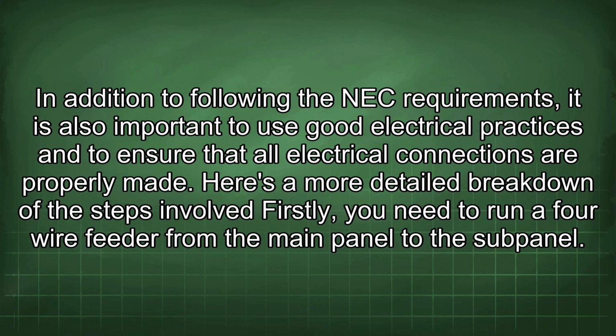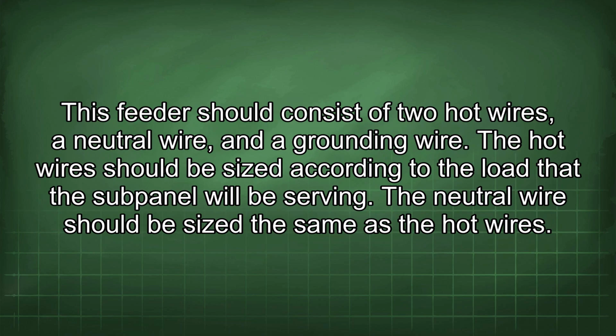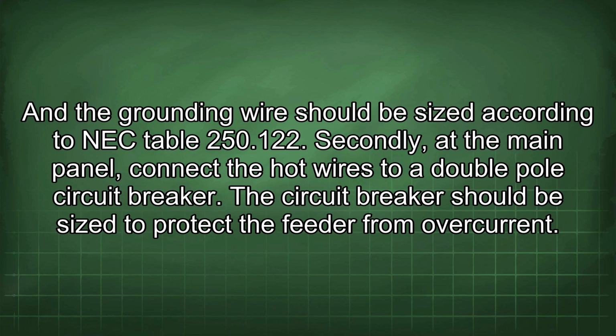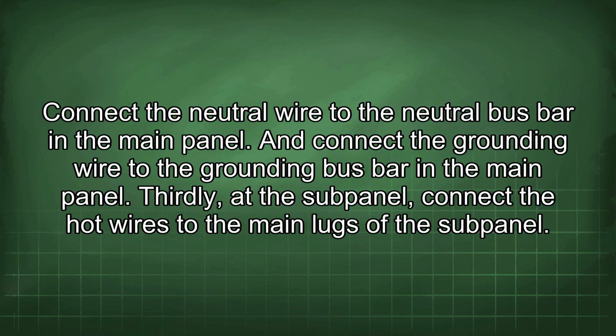Firstly, you need to run a four wire feeder from the main panel to the subpanel. This feeder should consist of 2 hot wires, a neutral wire, and a grounding wire. The hot wires should be sized according to the load that the subpanel will be serving. The neutral wire should be sized the same as the hot wires, and the grounding wire should be sized according to NEC Table 250.122. Secondly, at the main panel, connect the hot wires to a double-pole circuit breaker. The circuit breaker should be sized to protect the feeder from overcurrent. Connect the neutral wire to the neutral bus bar in the main panel, and connect the grounding wire to the grounding bus bar in the main panel.